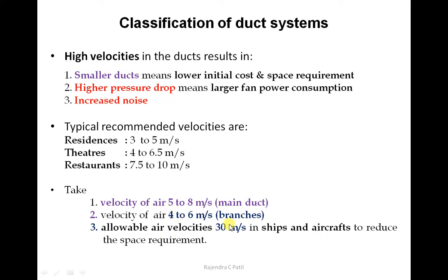For designing main ducts — which branch from AC equipment to the conditioned space — if velocity data is not available, you can take 5 to 8 m per second for the main duct and 4 to 6 m per second for branch ducts. The main duct near the AC equipment should have higher velocity than branch ducts. For ships and aircraft where space is critical, allowable air velocity is nearly 30 m per second.